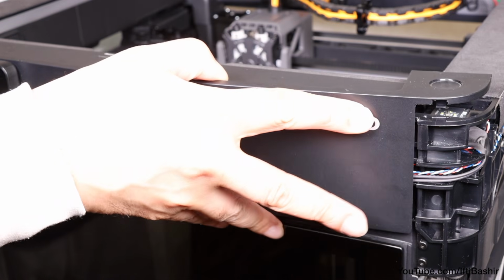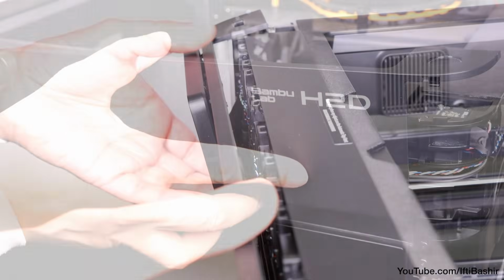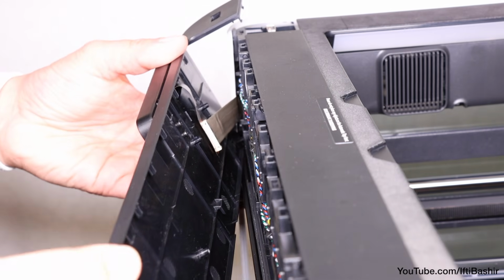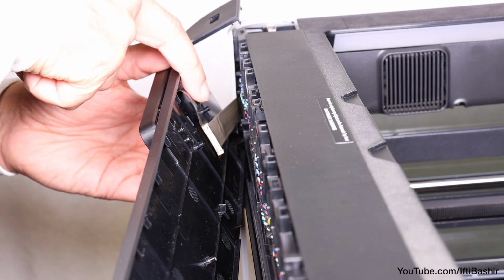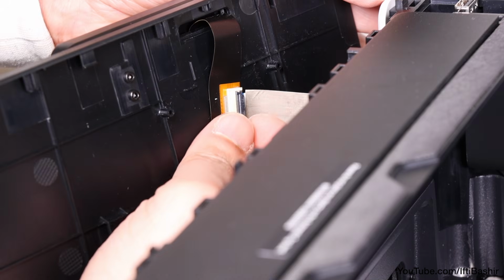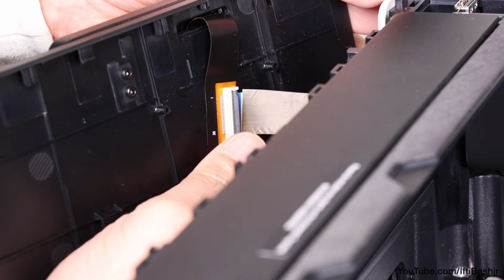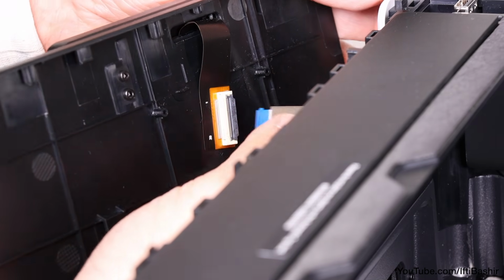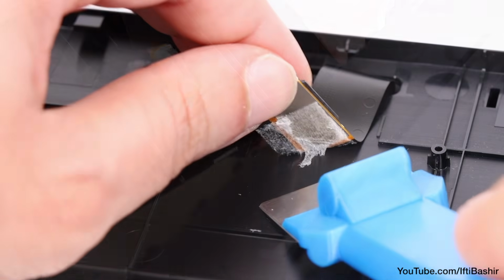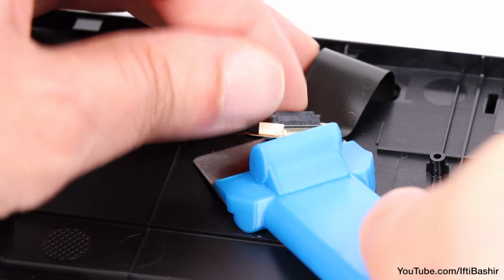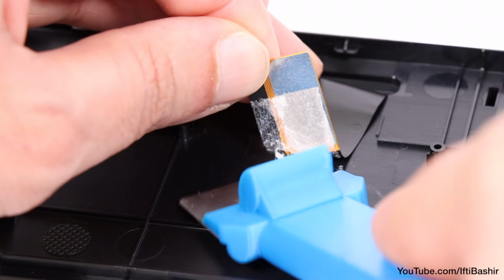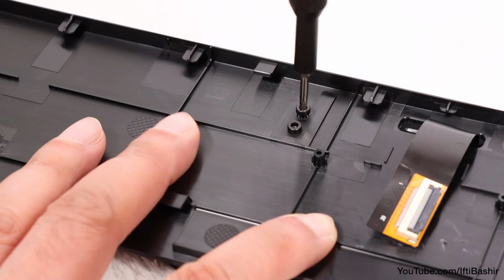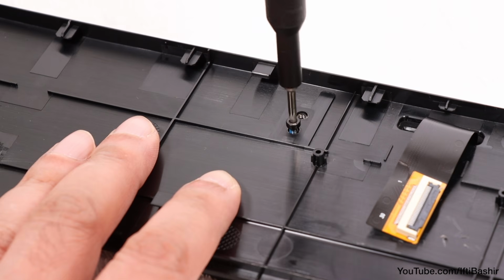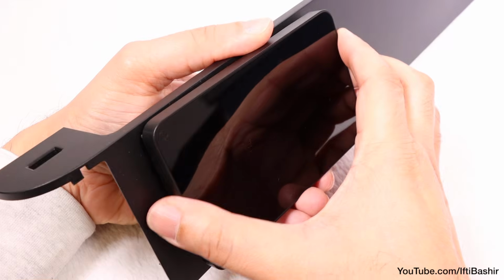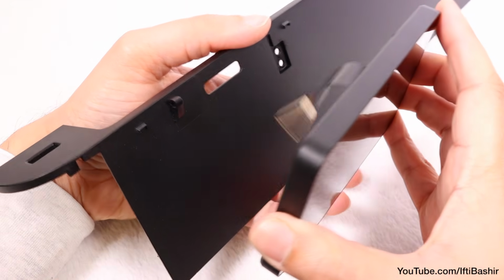Next, pull it from the right side panel, although do not pull away too far as the display cable is connected to the printer with a delicate ribbon cable. So proceed to lift the locking latch and remove the ribbon cable with care. With the panel now released, we need to remove the display. To do this, gently remove the adhesive beneath the connector, and once free, release the 2 screws holding the display in position, before releasing the screen completely.